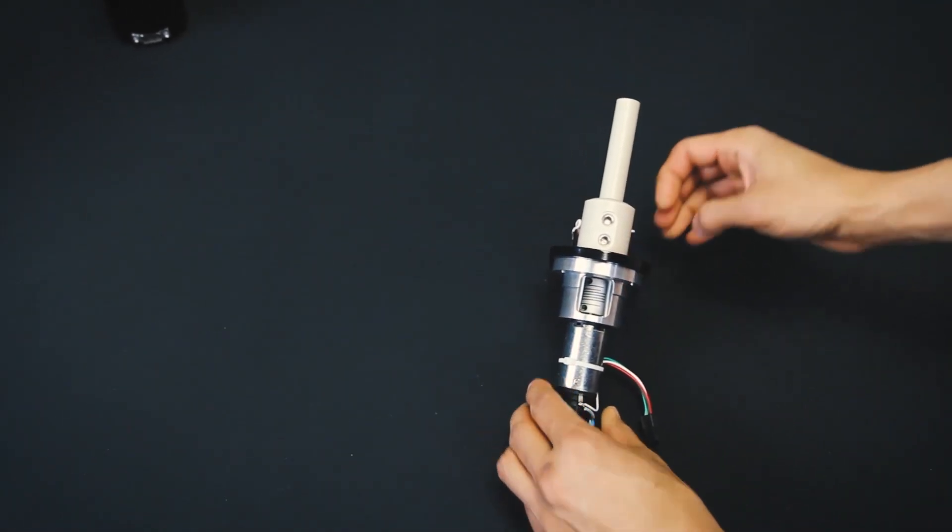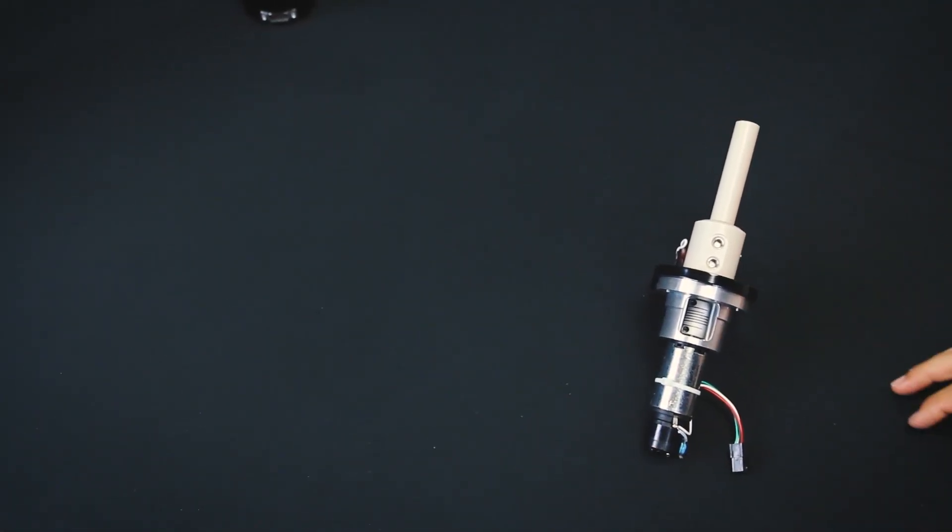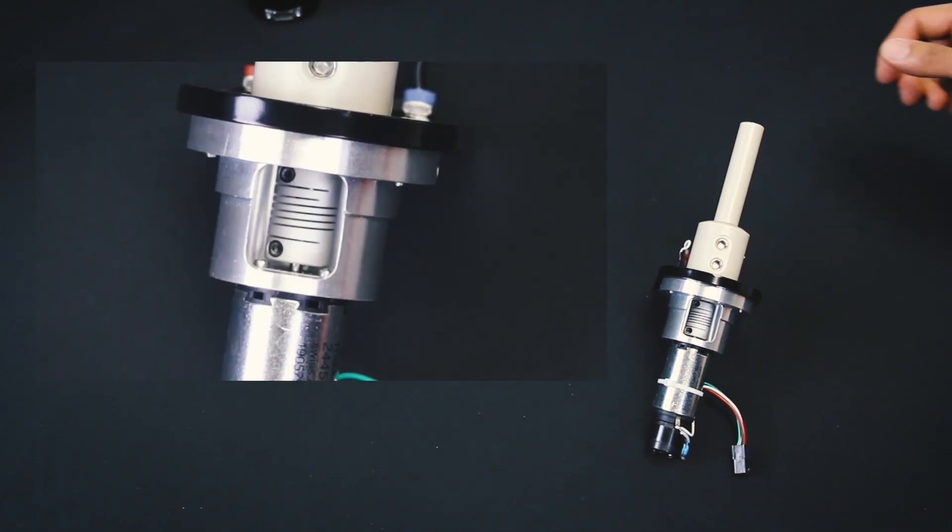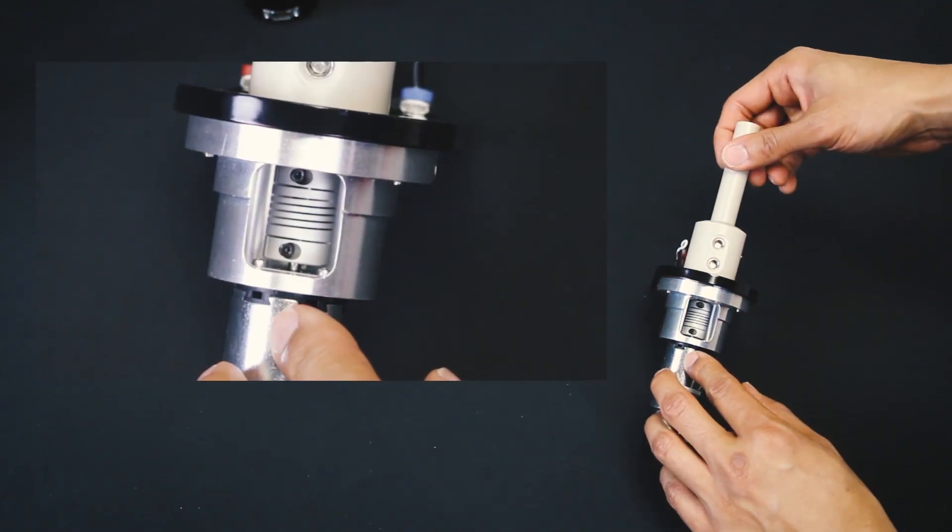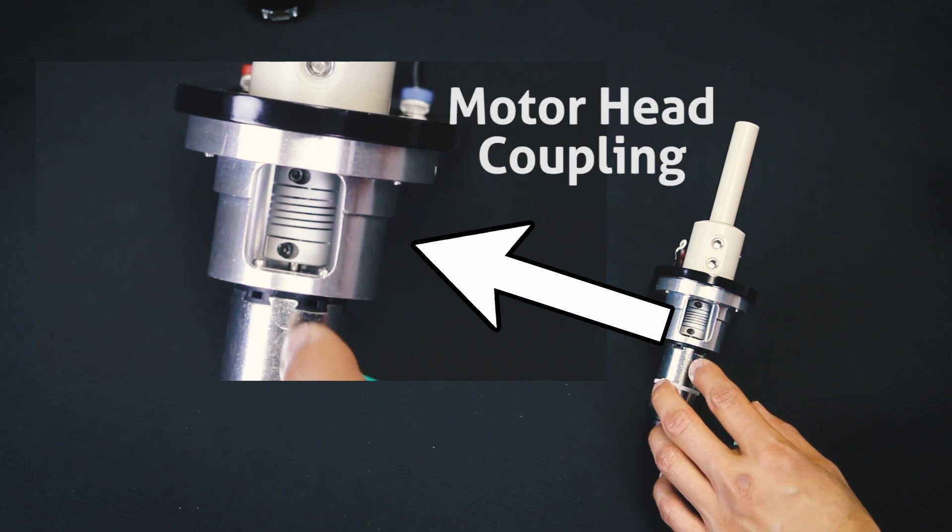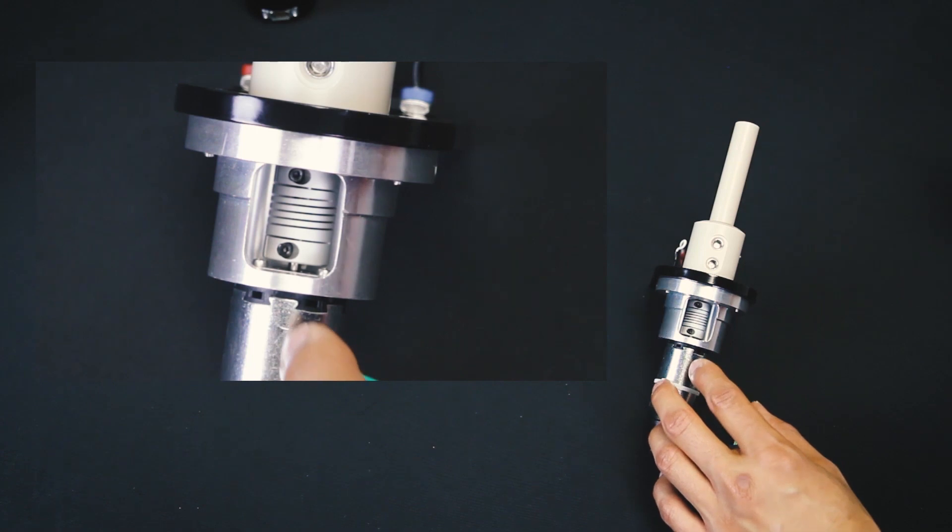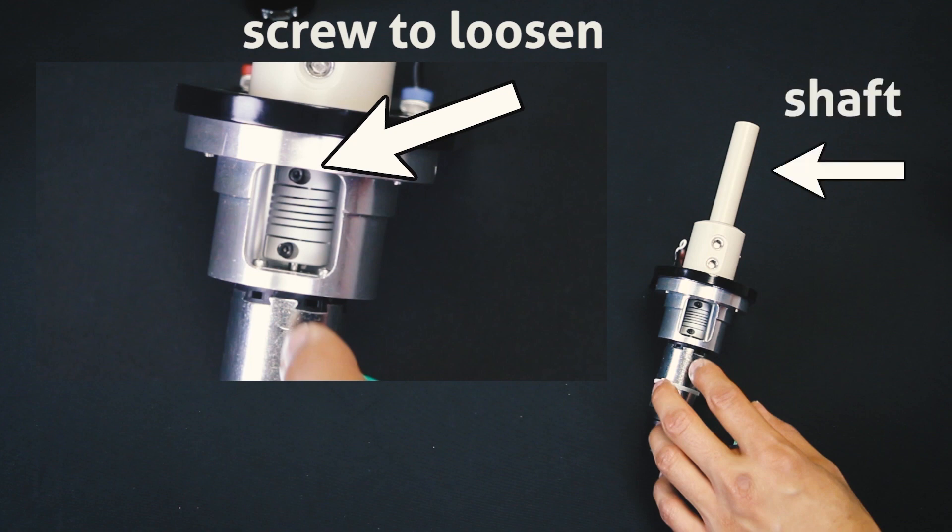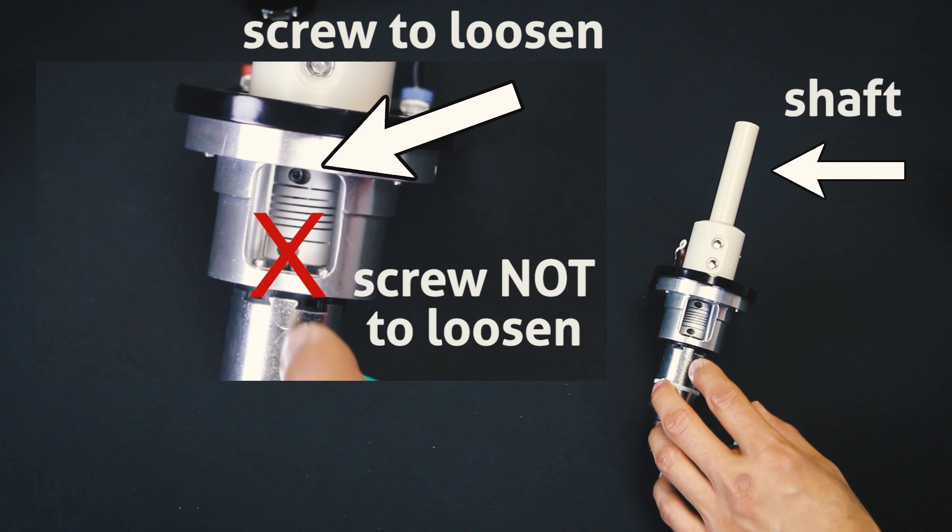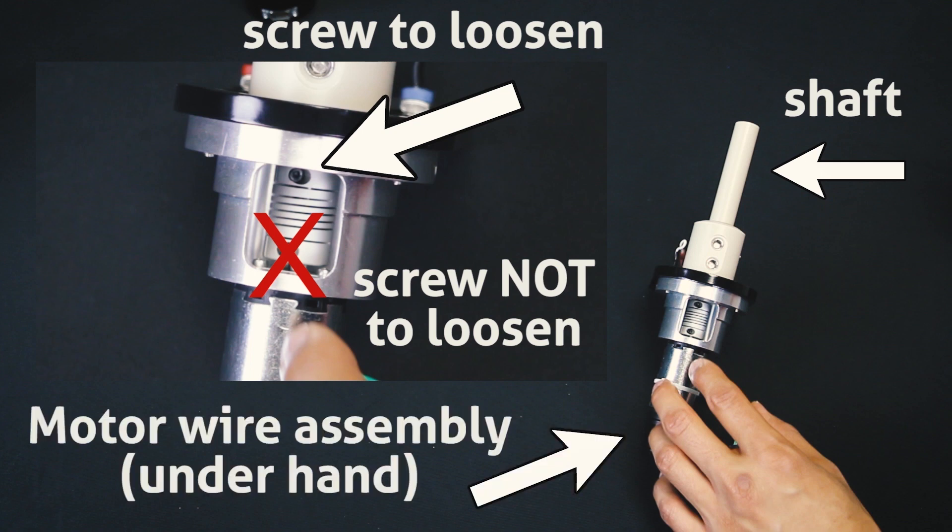Now we have the motor head. If you look here, there is a gap in the motor head where you will see the motor head coupling. The motor head coupling has two hex screws. Loosen the hex screw that is closer to the shaft using the 1/16th of an inch hex driver. Do not touch the hex screw that is closer to the motor wire assembly.